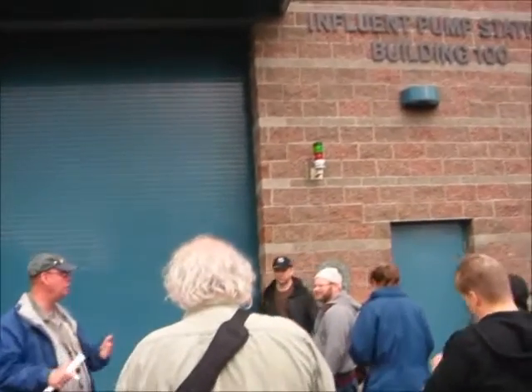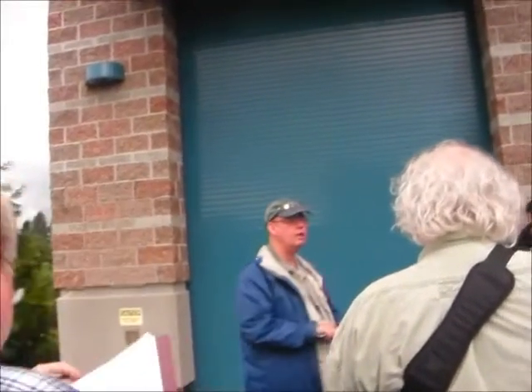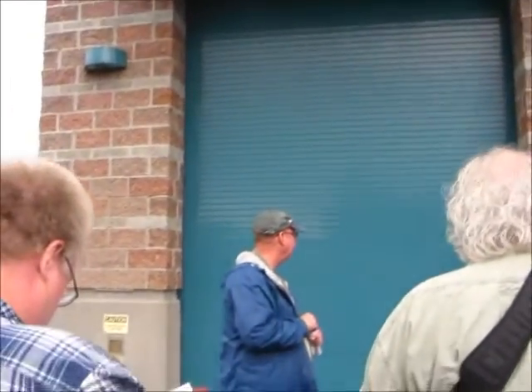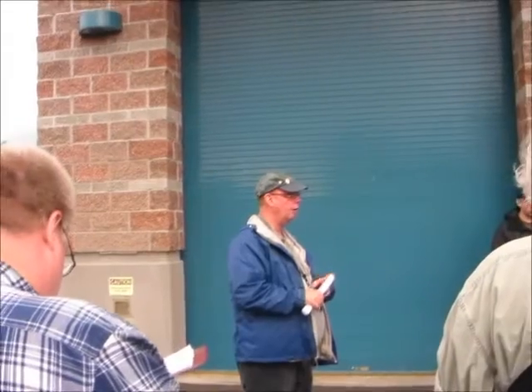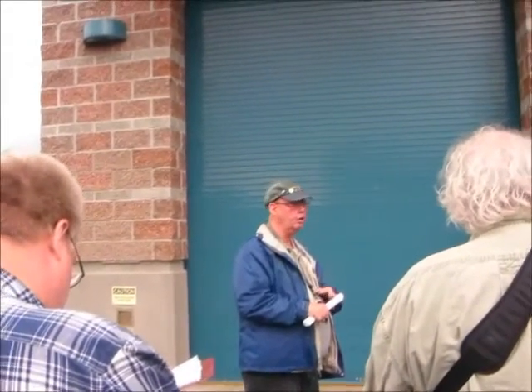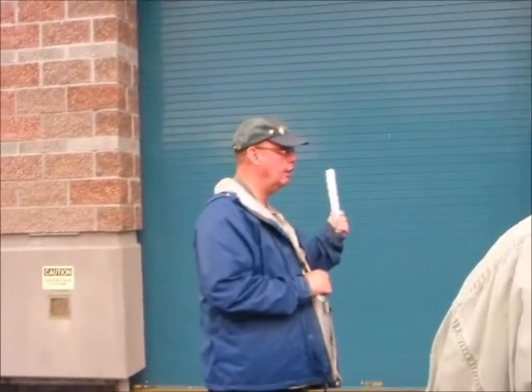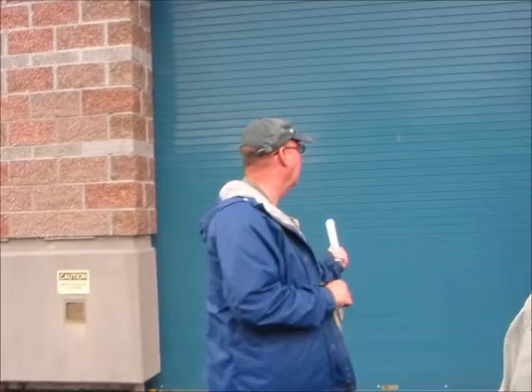This is our Influent Pump Station. Council, we'll go take a look at it. It is, as far as I know, the only pump station that has LEED certification. LEED is Leadership in Energy and Environmental Design. We incorporated multiple energy-saving options in here. All of our VFDs and all of our pumps use premium efficiency motors. And we try to do as much heating as we can. With cooling, we use our plant water, and for heating, we actually recover heat from our digestion process and send the hot water down here to help heat it.